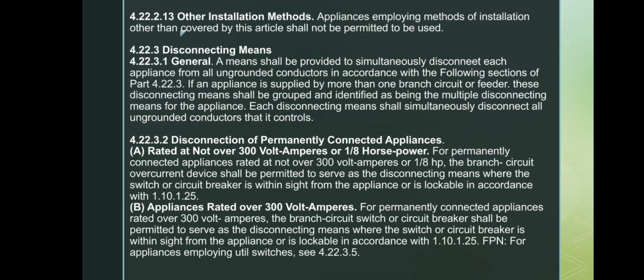For a permanently connected appliance rated 300 volt amperes or 1/8 horsepower or less, the branch circuit breaker or switch may act as the disconnect as long as it is within sight of the appliance or can be locked in the off position. For appliances rated over 300 volt amperes, the branch circuit switch or breaker may also serve as disconnect if it is within sight of the appliance or lockable. A note reminds installers to check additional rules for appliances that use utility switches.